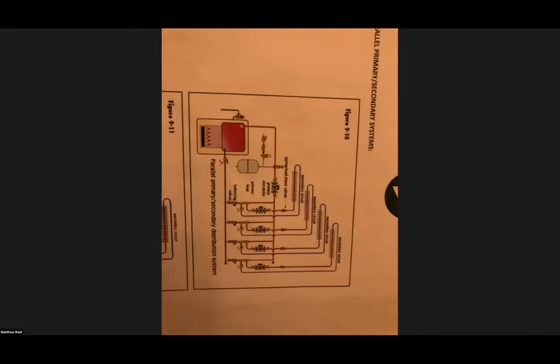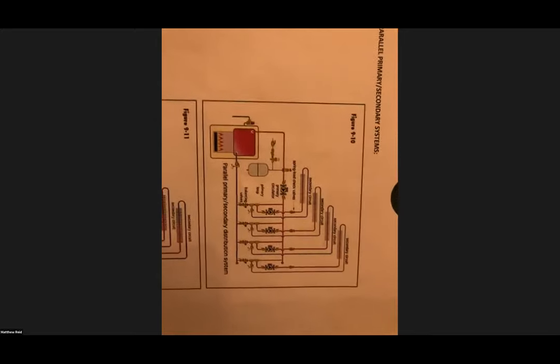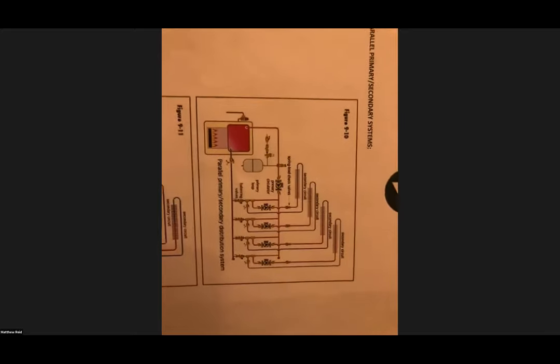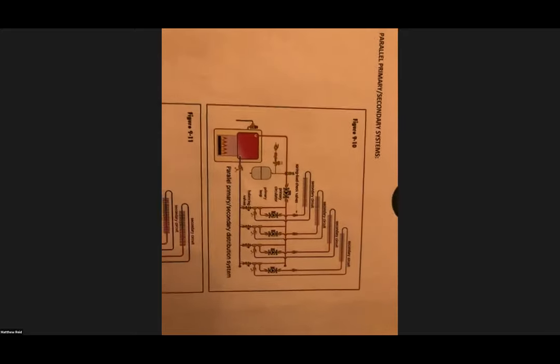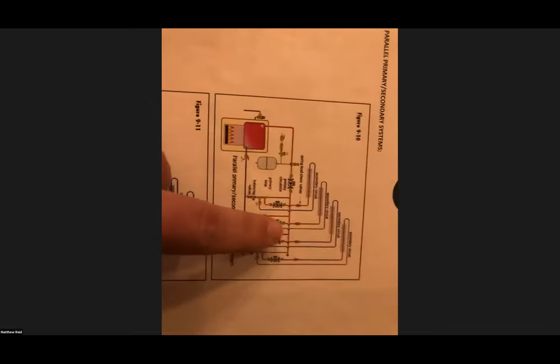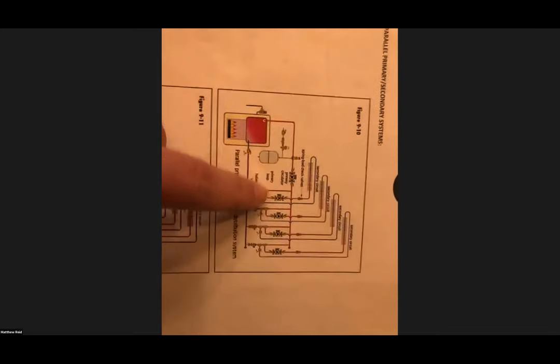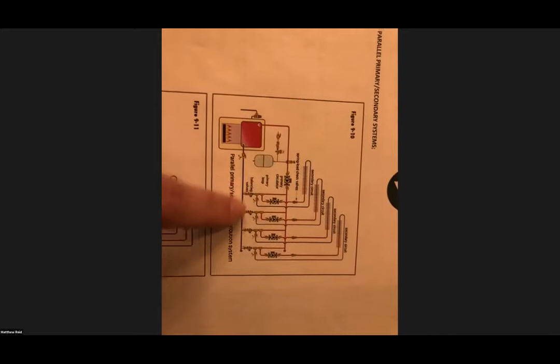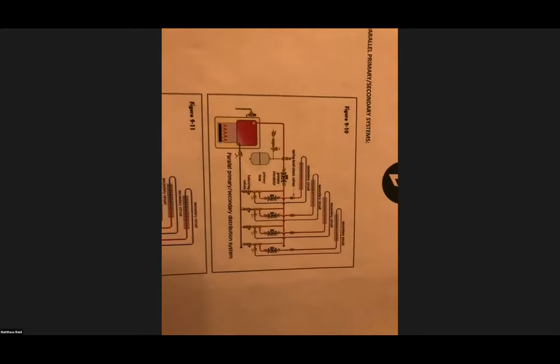I don't do a whole lot like this anymore. It's the same as doing injection mixing. I just don't do those anymore. There's no need for that. We have better pumps and better system designs to do that. However, what we're showing you is systems that work. So you're going through your branch supply header, and then your set of closely spaced T's for each loop is coming out, and then a balancing valve for your return.